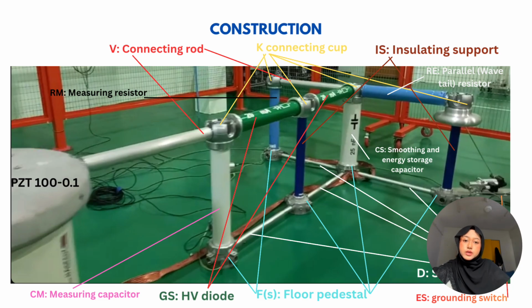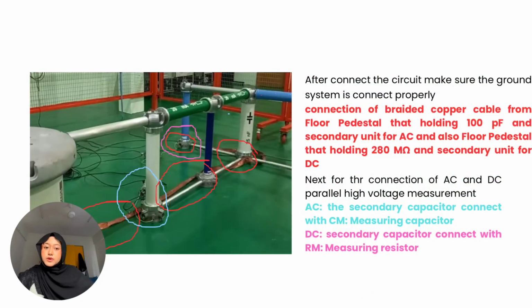So this is our construction in Lab 3. After we connect the circuit, we must make sure the grounding system is connected properly. The circled red one is the connection of braid copper cable from the floor pedestal holding 100 picofarad and the secondary unit for AC, and also the floor pedestal holding 280 megaohm and the secondary unit for DC. Next, for the connection of AC and DC parallel high voltage measurement, the blue one is AC. It's the secondary capacitor connected with the CM measuring capacitor. And the pink one is the DC secondary capacitor connected with the RM measuring resistor.